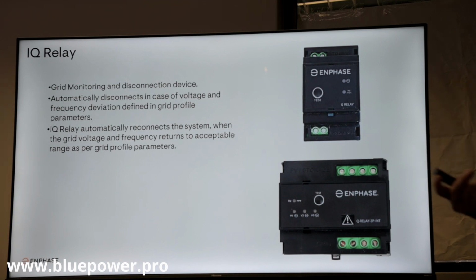And then when it sees that the grid is stabilized and the frequency is stabilized, it will automatically reconnect the system again to the grid. Remember, these are grid-tied inverters, right? And the rating for this is IP21, so it's not IP67 like our other, like the microinverters. So obviously it needs to be inside or in an enclosure of IP67 rating.